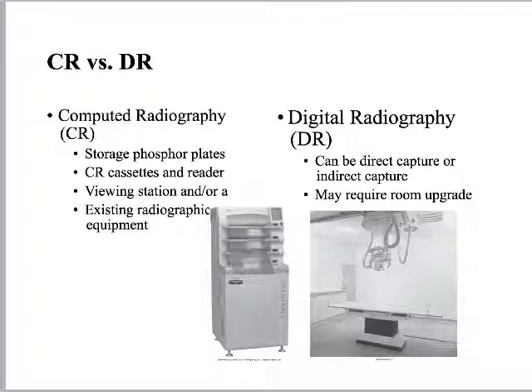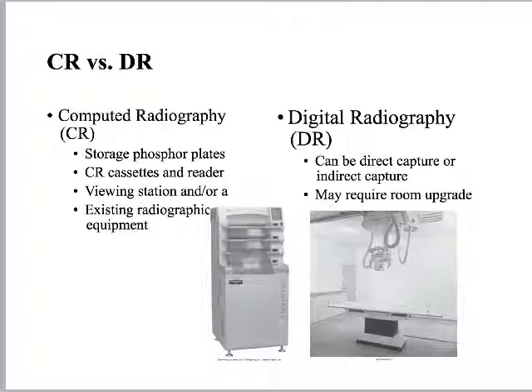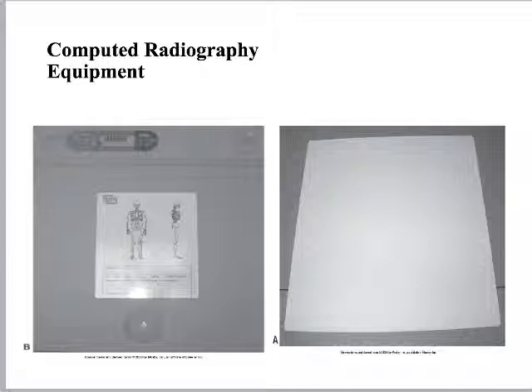CR versus DR — we're pretty familiar with the distinctions because they create major differences in everyday x-ray department workflow. CR uses storage phosphor plates inside CR cassettes, a CR reading station, and a viewing station before sending images to PACS. DR may require a room upgrade, and a lot of times you take the picture and it just pops up on your computer screen with no additional reading required.